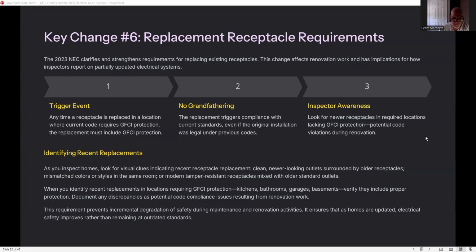This requirement prevents incremental degradation of safety during maintenance and renovation activities. It ensures that as homes are updated, electrical safety improves rather than remains at outdated standards. So it's a little difficult, because if you've had a renovation done by a contractor, hopefully they pulled a permit. They didn't have to, but hopefully they did. If they pull a permit, then the town has gone in there and checked this. But if the homeowner is just replacing outlets that are ugly and they need to be GFCI protected, they don't know that, and you're seeing the new outlets, you're going to call that out too. So you've got to look for everything.